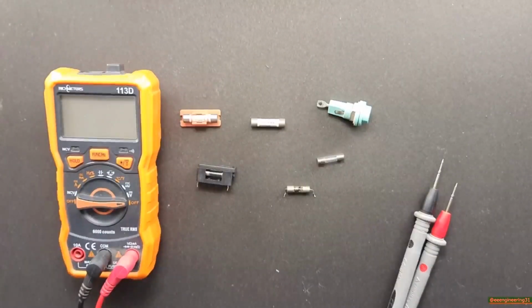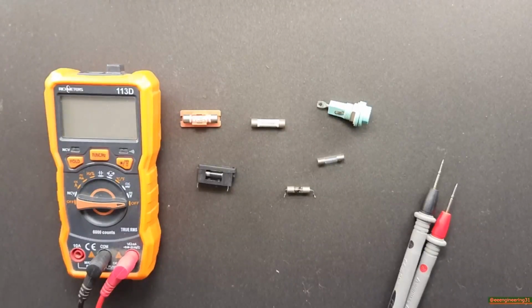Now, how to repair the fuses? You should replace fuses with the exact type or some lower value. For example, you can replace a 12 ampere fuse with a 10 ampere fuse of the same type. You should never exceed the rating of the fuse that was originally in the device itself.